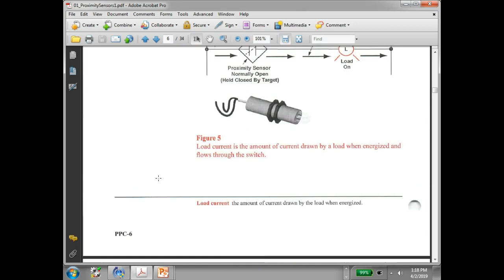So your load current is going to be the operating current plus the actual true current of the load. So on this one, the load current is the current required to make the solid state operate, plus the actual current of the load. Does that make sense? That's not the operating current—that is the load current.